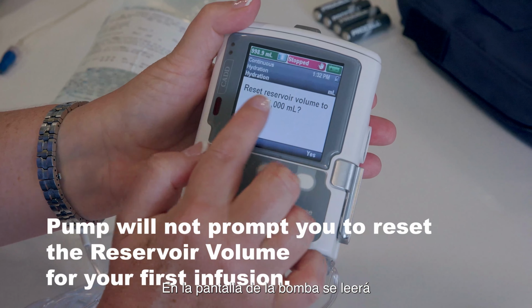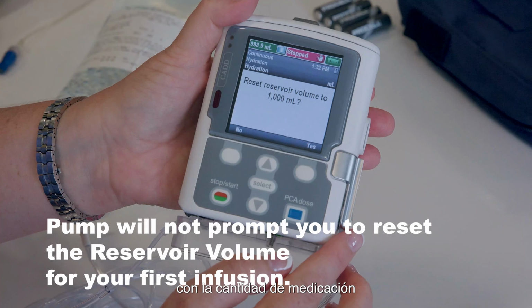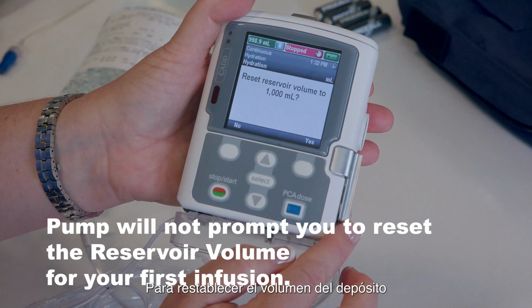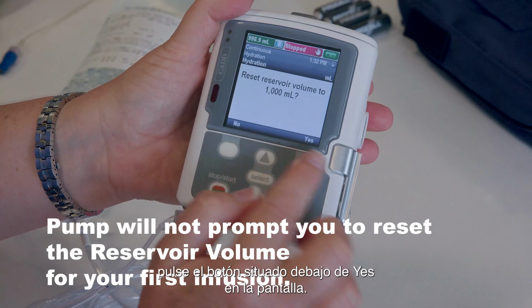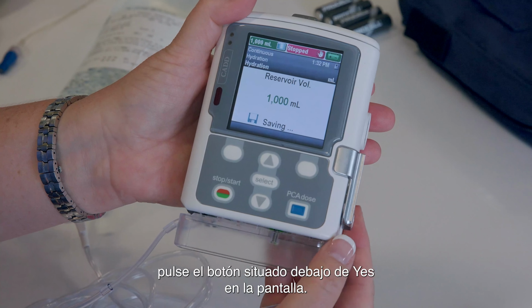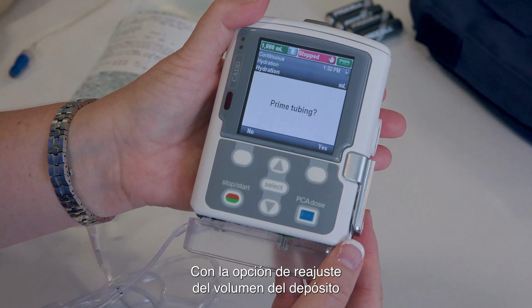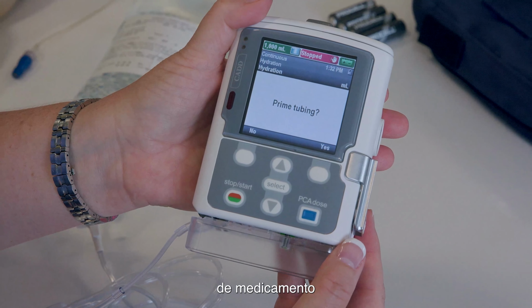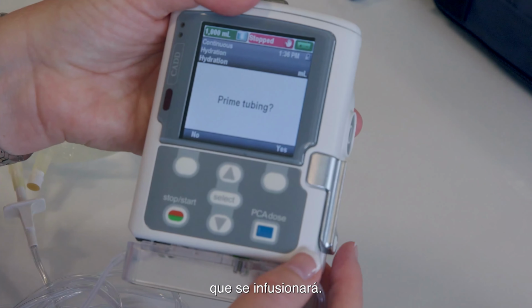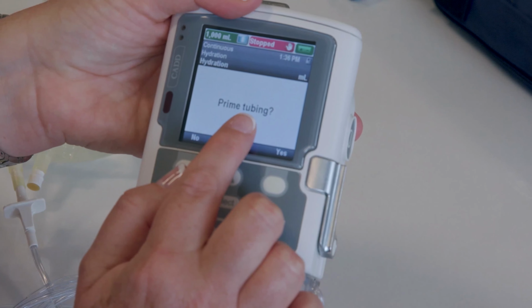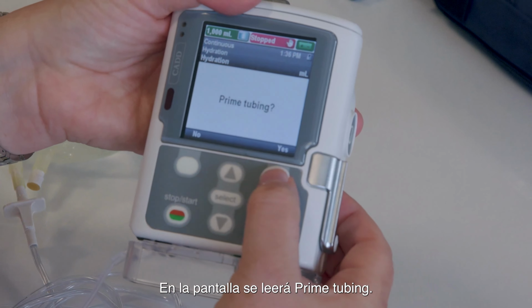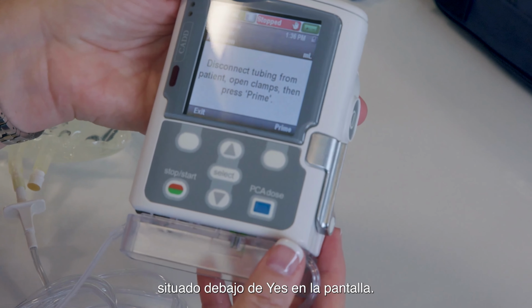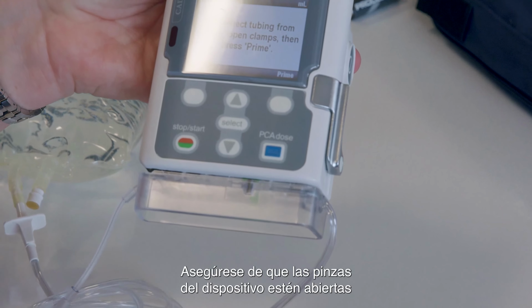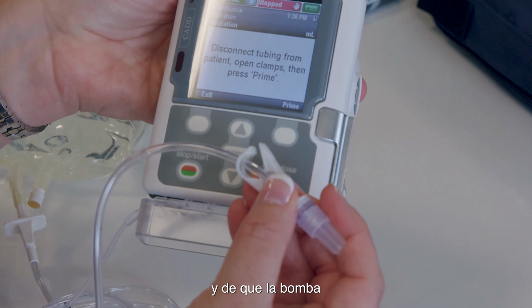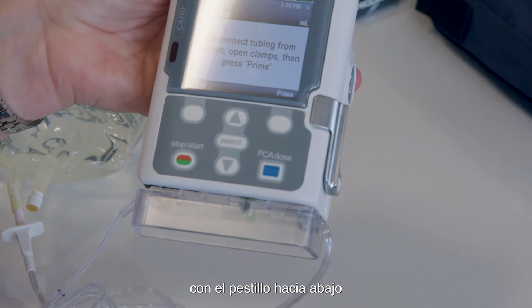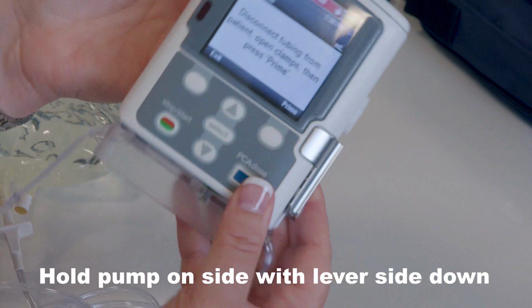The display will read, Reset Reservoir Volume with the pre-programmed amount of medication. To reset the reservoir volume, press the soft button under Yes on the screen. Resetting the reservoir volume will change the amount of volume to be infused to the pre-programmed prescribed amount of medication. The display will read, Prime Tubing. Press the soft button under the word Yes on the screen. Make sure tubing clamps are open and the pump is turned on its side with the lever side down to assist with removal of air bubbles.